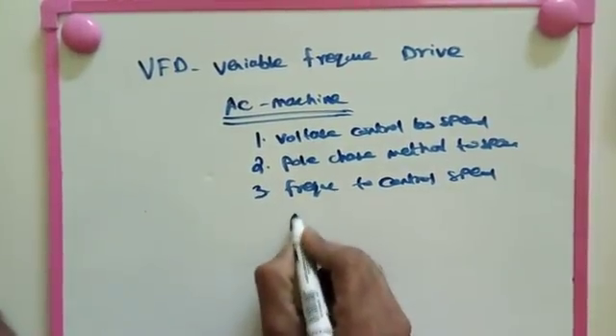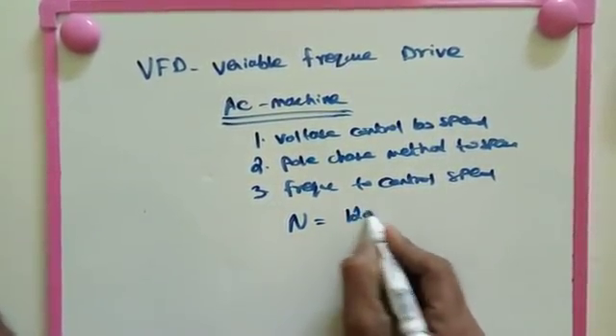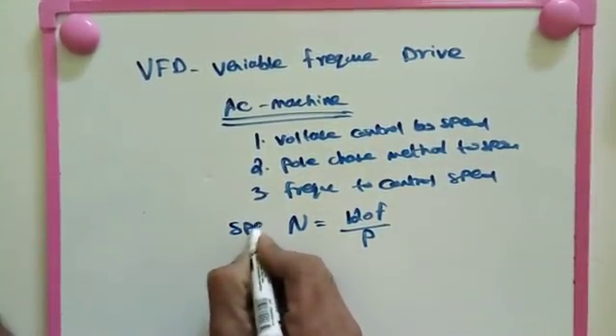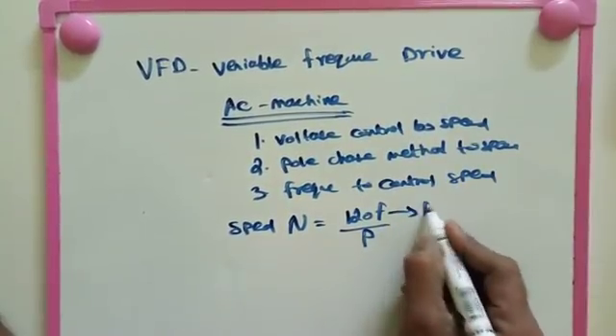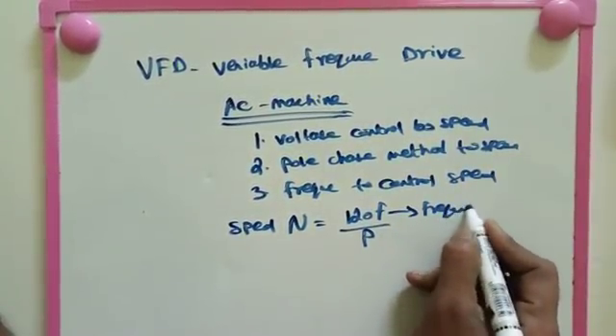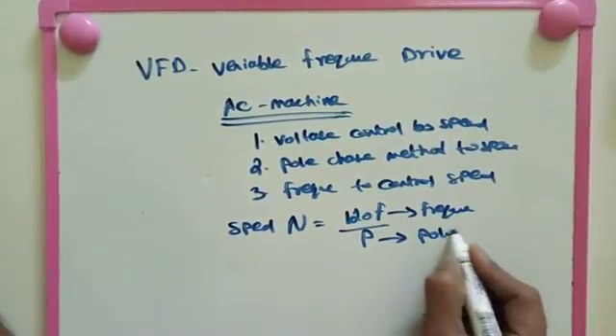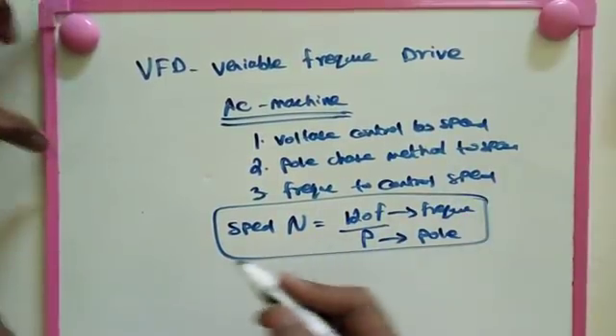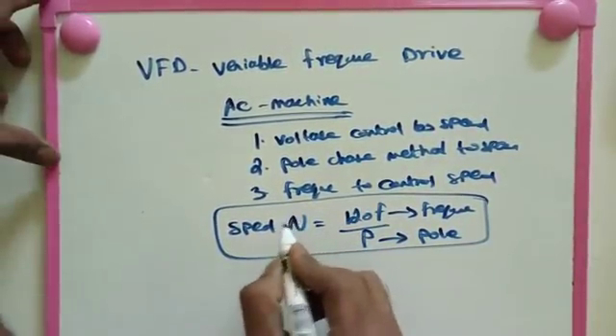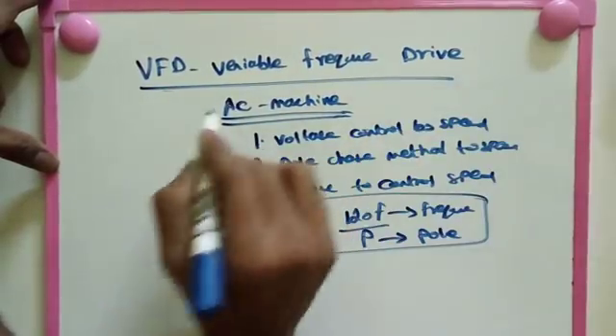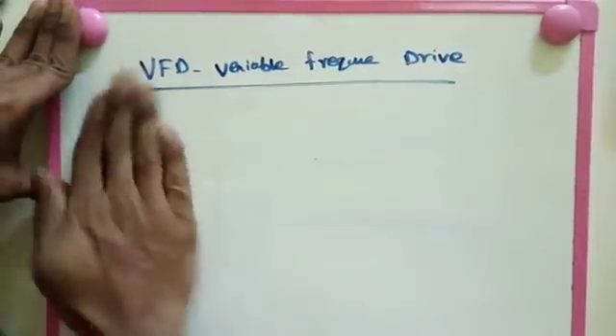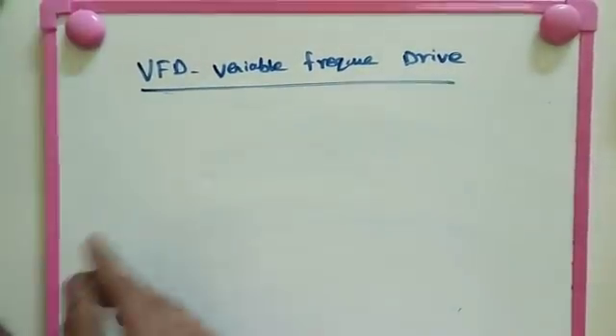The speed formula is N equals 120F divided by P, where N is speed, F is frequency, and P is poles. We are going to use the frequency method for AC machine speed control. This method is what we call variable frequency drive.